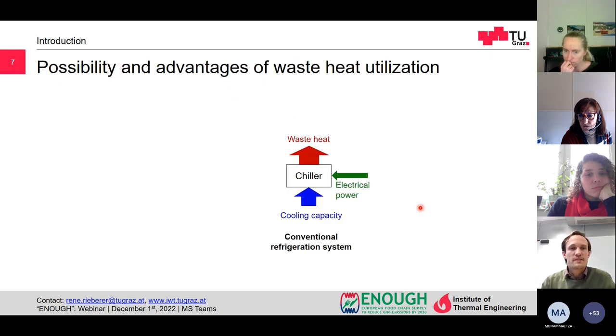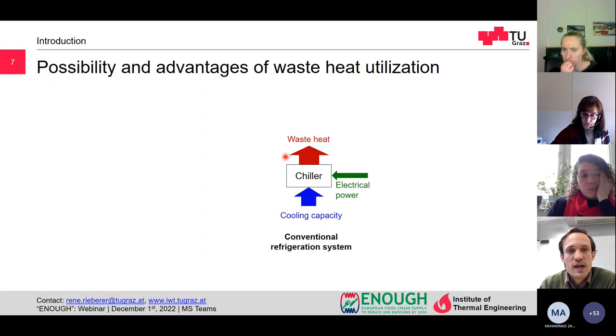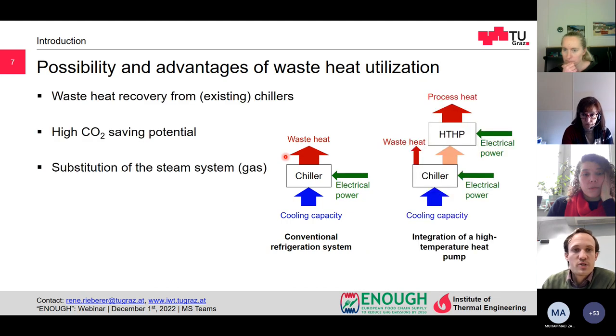What are now the possibilities and the advantages of waste heat utilization? In general, we have a conventional refrigeration system, which is needed to supply cooling capacity for the cooling processes, and the waste heat is usually rejected to the ambient by cooling towers. And in the project in ENOUGH, we are looking into this waste heat utilization with a high temperature heat pump.